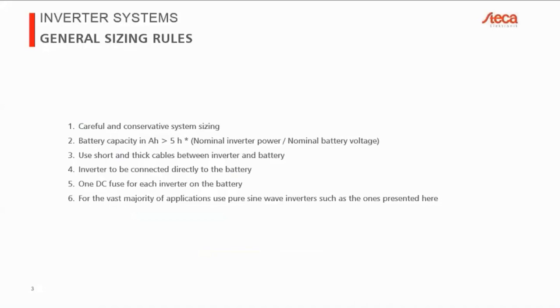So just to give you an example, if you have a system which, let's say, consumes 1 kilowatt-hour per day, that is your consumption. So your PV modules, your batteries, also your charge controller, everything will be designed based upon this assumption that your customer is really consuming 1 kilowatt-hour per day. If by chance your customer is using 2 kilowatt-hours per day, then even if you've done your job correctly as a systems designer and installer, of course the PV production will be too low for this much higher energy consumption than you initially expected.